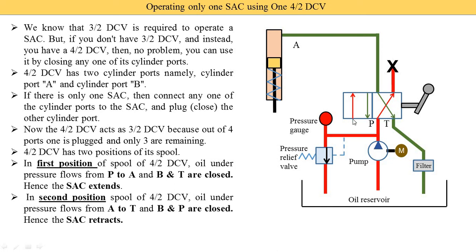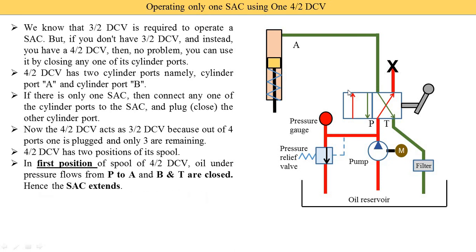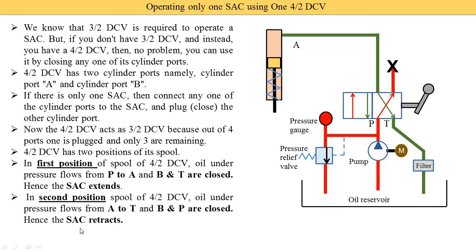The return path A to T is open. Port A is connected with port T. How does oil come back into port A? In the earlier case we supplied P to A. But here we use a single acting cylinder of spring return type. When the extension is complete, the piston starts to move from the bottom to top — upward — due to the spring force. As the piston moves up, the oil in the upper part of the cylinder is pushed into the pipe, comes through the green pipe into port A, goes from port A to port T, and returns to the oil reservoir through the filter. During the second position, the cylinder retracts.